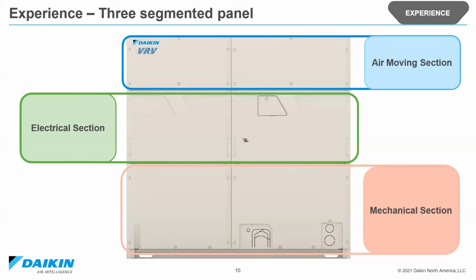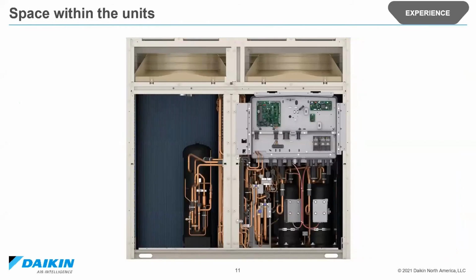With this version, the front of the units now have a 3-segment panel design. This eases service and maintenance. And then an additional service window is also included that provides quick access to the multifunctional display and configuration buttons. So it's easier to get to your controls. Upon opening the 16 to 20 ton cabinet here, you can see the increased space inside the unit. Enhanced dust and moisture protection has been added to the patented electrical box, as well as an IP55 rating.